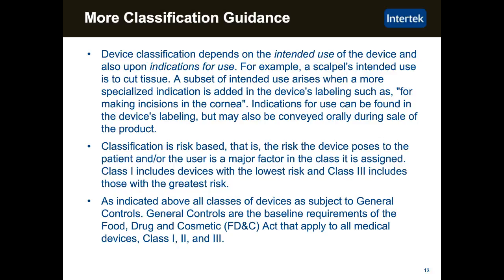As I said, classification is risk-based. That is, the risk of the device as it is posed to the patient or the user is a major factor in what class it is assigned. Class 1 includes those devices with the lowest risk, and Class 3 includes those devices having the greatest risk. As I mentioned above, all classes of devices are subject to general controls, and the general controls are the baseline requirements from the Food, Drug, and Cosmetic Act that apply to all three classes of device, 1, 2, and 3.